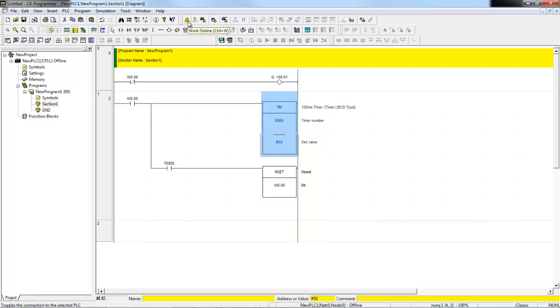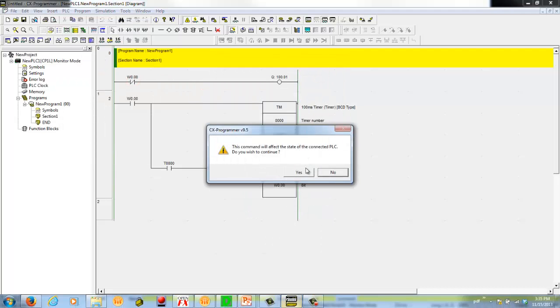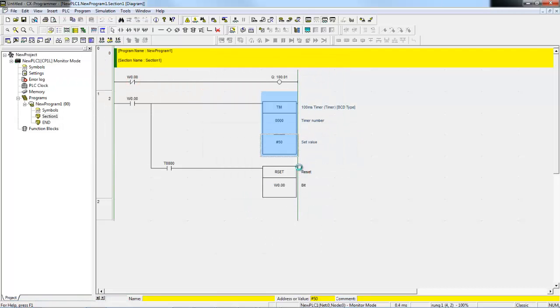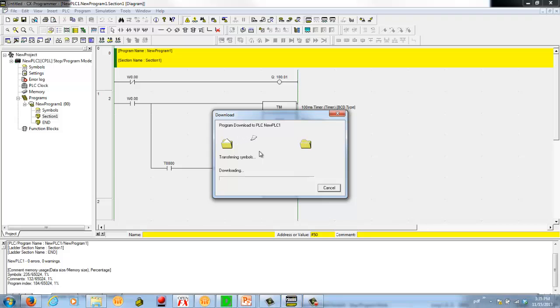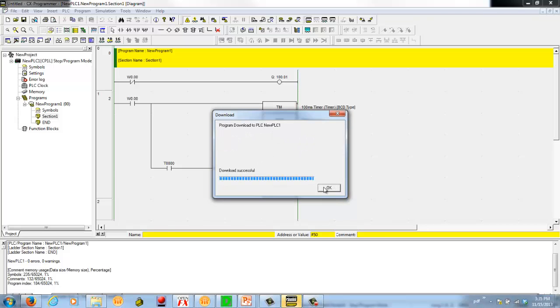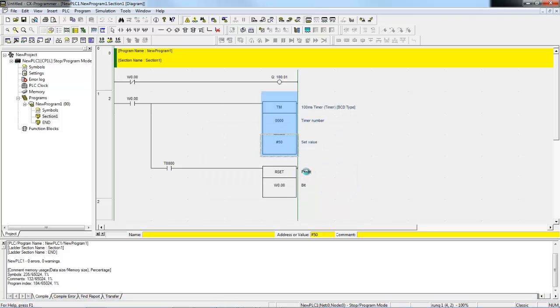Now I can work online, and I'm going to PLC, Transfer to PLC. Select OK. It just switched the PLC into Program mode for me automatically, and when it's done, it asks me do you want to switch back into Monitor mode, and I'll say yes. So actually most of the mode handling is handled automatically by CX Programmer for you.